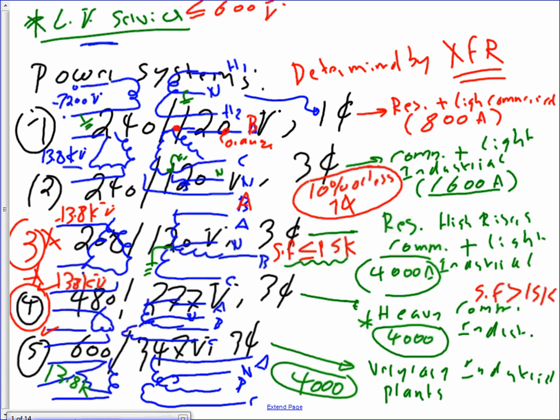One more time. You start with the first one, residential 240/120. The second one is 240/120 3-phase, typically commercial industrial with only a small amount of single-phase load. The most common ones, guys, in the US that we use in industrial and commercial are number 3 and number 4. You can see that it's 208/120 and 480/277. These are the most common ones.